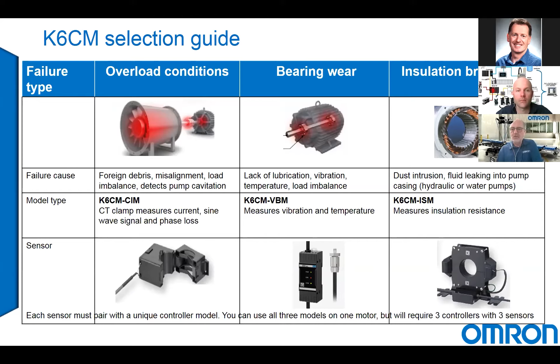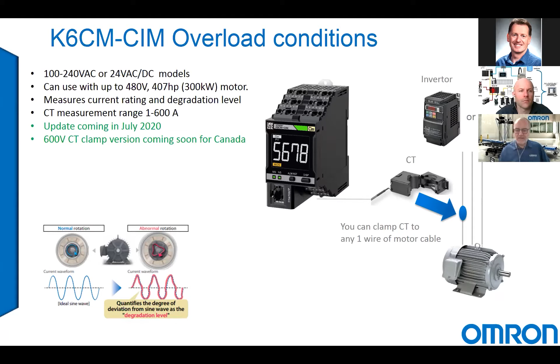So the overload condition, again, with these systems, we can monitor motors up to 480 volts, up to 300 kilowatt or 407 horsepower for that matter, up to 600 amps. We have CT clamps that we put on one phase of your motor, maybe powered by an inverter or a contactor, we don't care, but we're looking at the current sine wave. If we see that the sine wave is abnormal, when there's a degradation level, we trigger an alarm, and this alarm can be hardwired to the actual output on this relay, or can be monitored with the Ethernet IP connection.